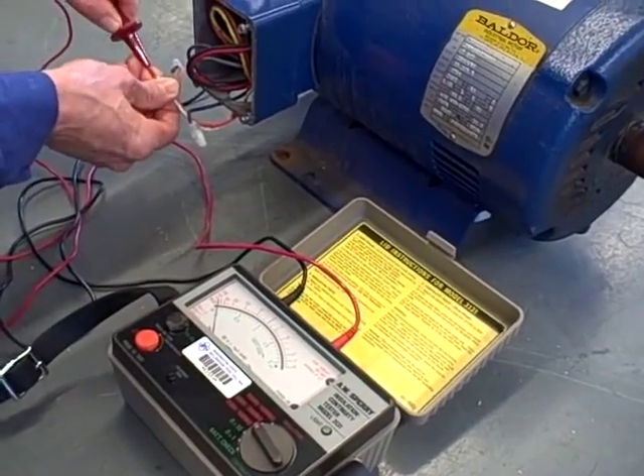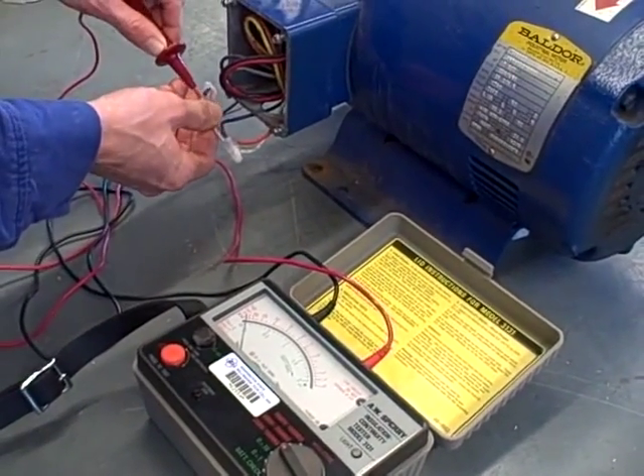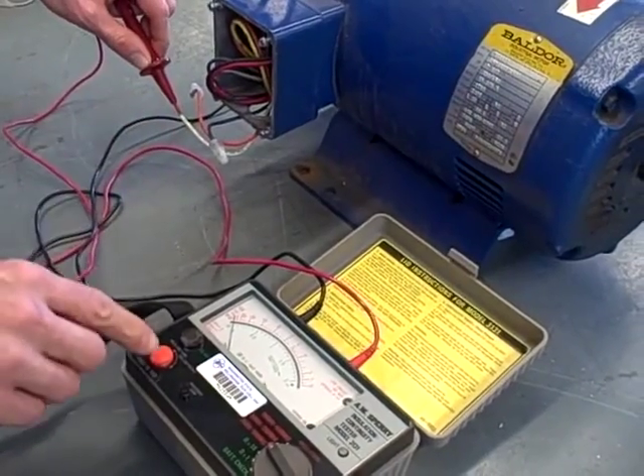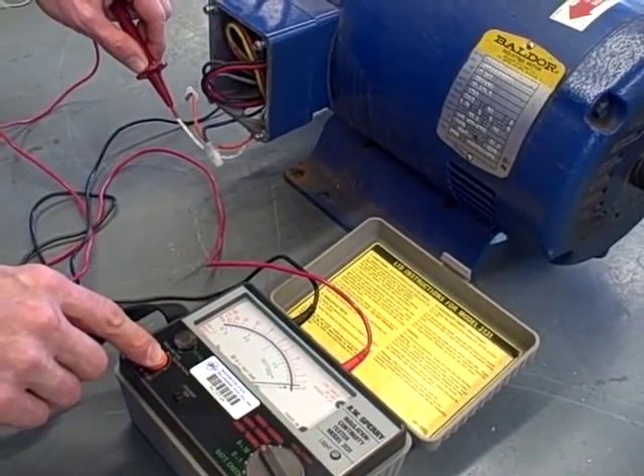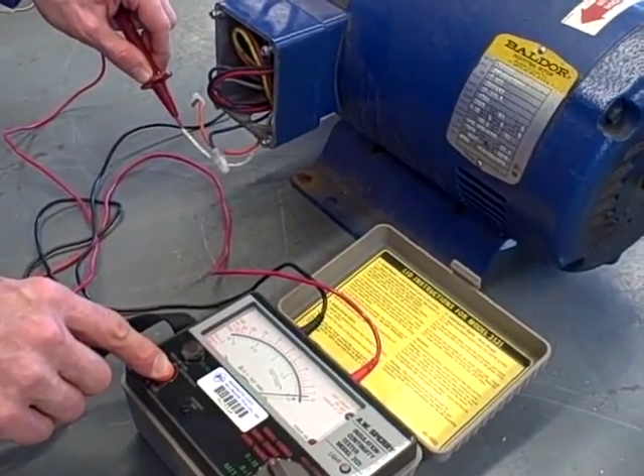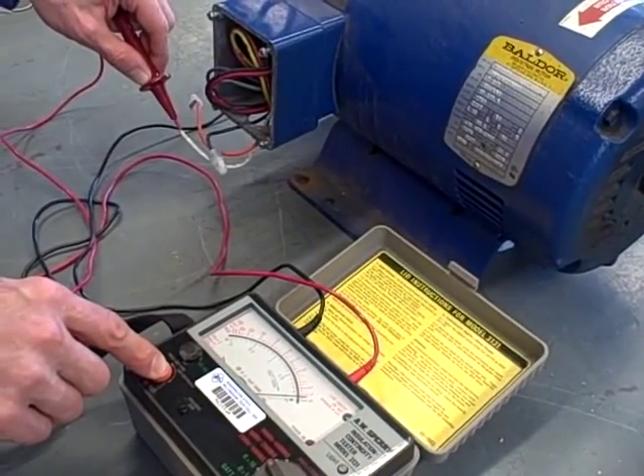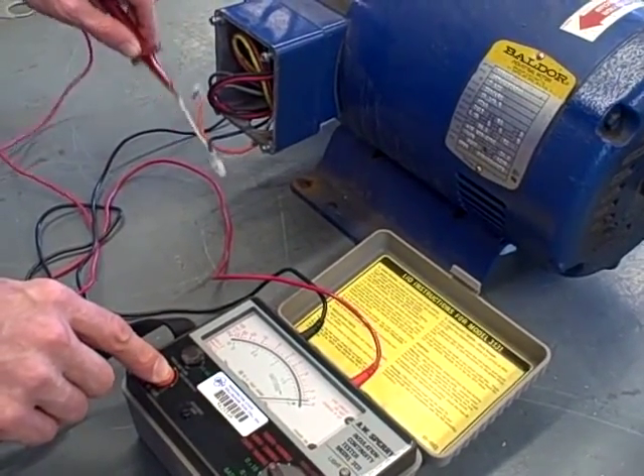So I come over here, make my connection. Just to prove again how this works, I've got my connection made. I'll push the button. It swings to the right, which means 0 ohms, or low resistance, in the high voltage mode. If I open this up, watch what happens. It swings to the left, meaning open.